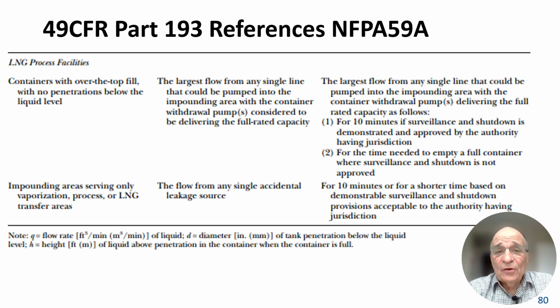Now, so far we've spoken only about tanks that have bottom penetrations. What about the tanks that don't have bottom penetrations but have internal tank pumps? Well, for those tanks, we have similar requirements, a guillotine cut of the piping. And for those tanks, we're going to look at the maximum flow from any single line that could be pumped into the impound area with the container withdrawal pumps delivering at full rated capacity as follows. For 10 minutes if surveillance or shutdown is demonstrated and approved by the authority having jurisdiction. For the time needed to empty the full container where surveillance or shutdown is not approved.